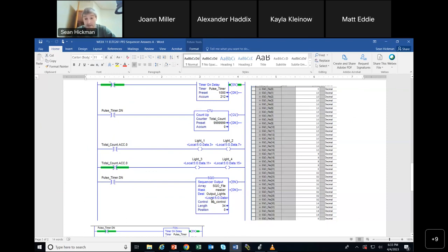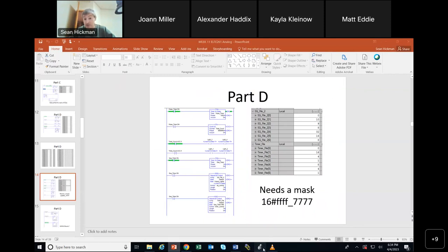And then this right here is telling the same light or output, number 3, to be on or off. You can't have two outputs, you can't have things coming on or things coming off. Does this make sense what I'm saying here? Yes or no, that these outputs are the same as these outputs. You're using an output twice. And we know that we don't want to do that. You only want to use an output once. But if we're using it twice, we can mask it out. My mask was called masker, so you mask out those. Let's mask those out so that we're not using that.